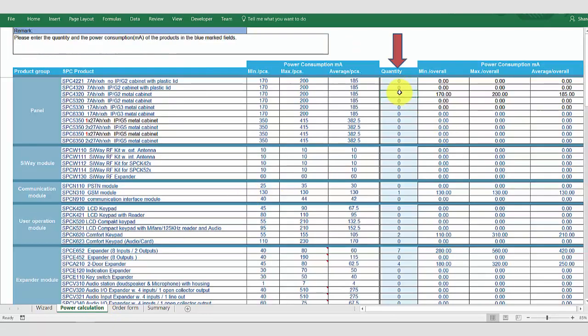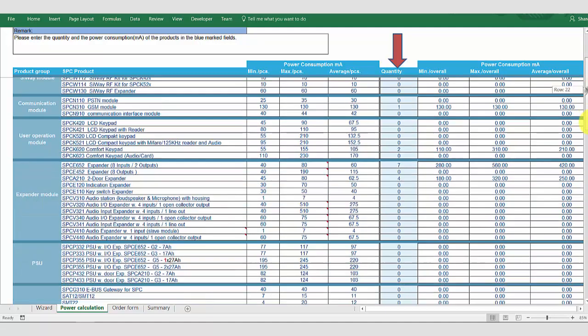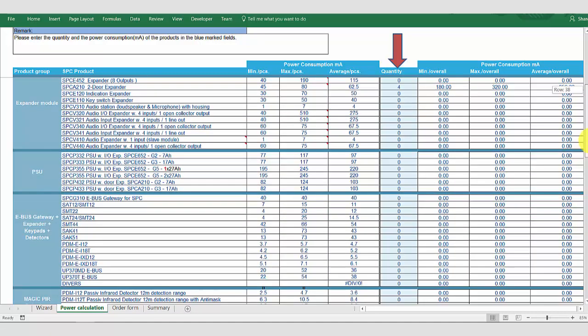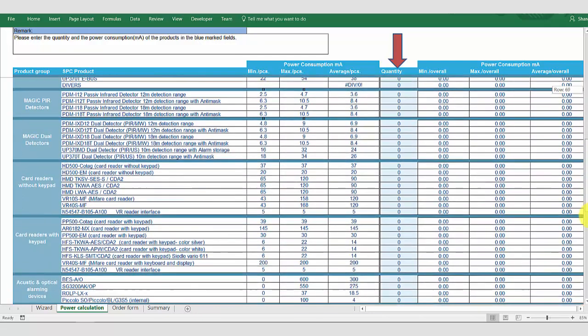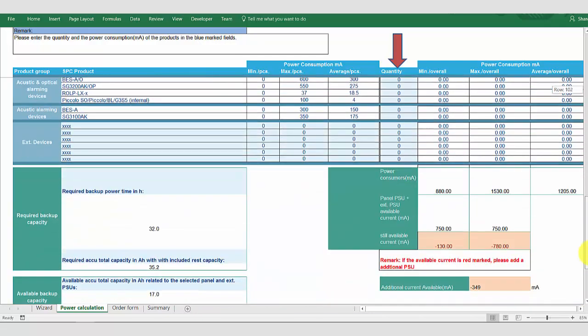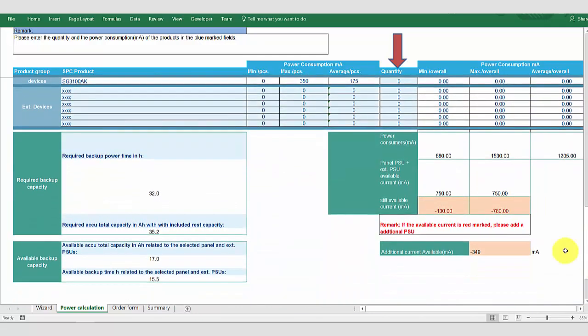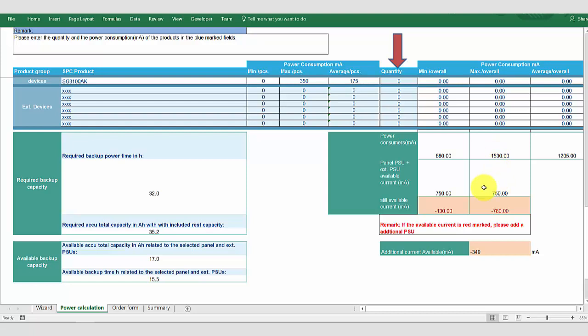So, returning to our system, we will restore to an SPC 5000 and we will continue with our system. First of all, we should take care to check that we have sufficient power. The tool will show what the minimum and maximum draw of the entire system is, if it is in alarm or idle state. And what we can see is that we have insufficient power in order to power the system.